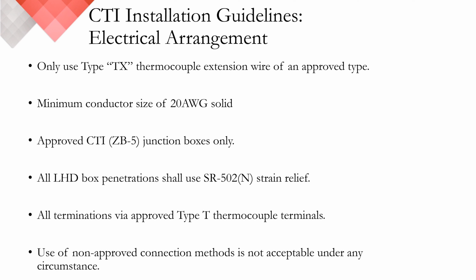As we illustrated previously, unlike our Legacy Series detector with steel and copper-covered steel conductors, the use of a Type T thermocouple cable to communicate an accurate temperature profile is critically important with the CTI Series detector. It's what sets it apart. Each connection point branching from the interface module and in contact with the CTI detector must maintain this principle of dissimilar metals, and these two metals are copper and constantan. It's also crucial to view these two metals as your polarity.